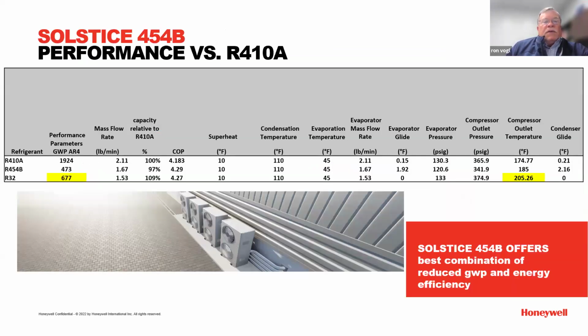A little bit more on the air conditioning replacements. This is how they perform. 410A, and you've got 454B and 32. The flow rates are a little bit less than 410A. One thing I will point out when you take a look at outlet, the one issue with 32 is the higher discharge temperatures. You need to be aware of that.